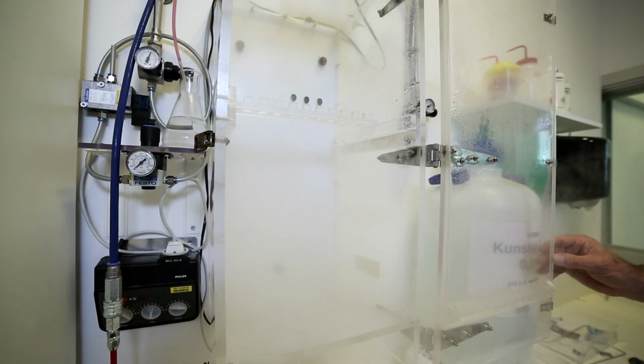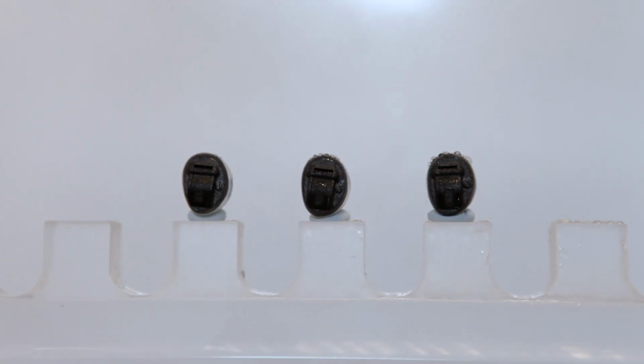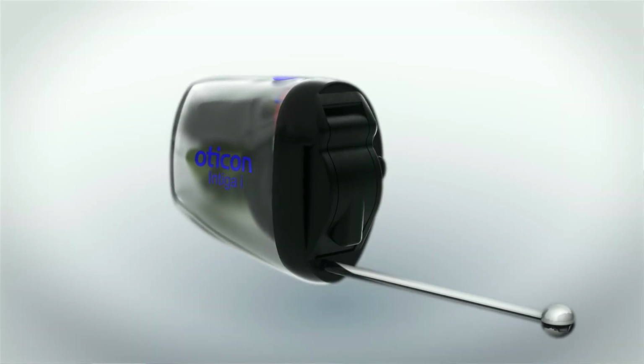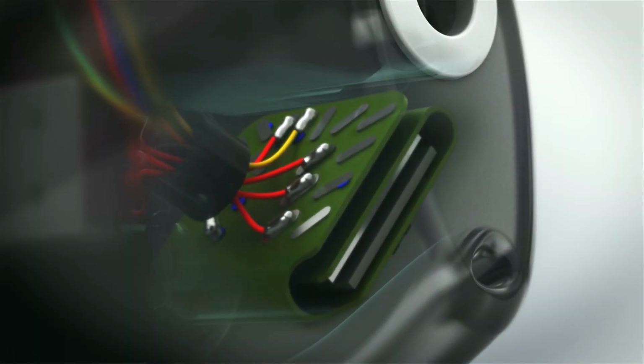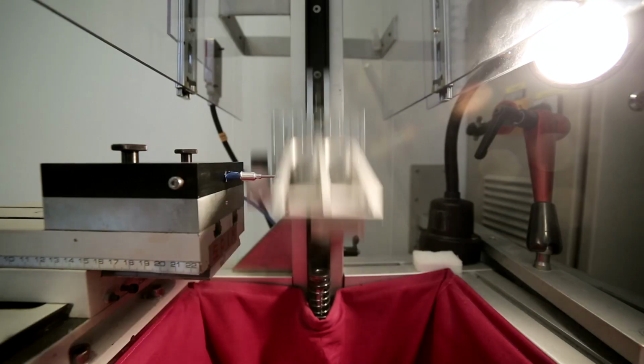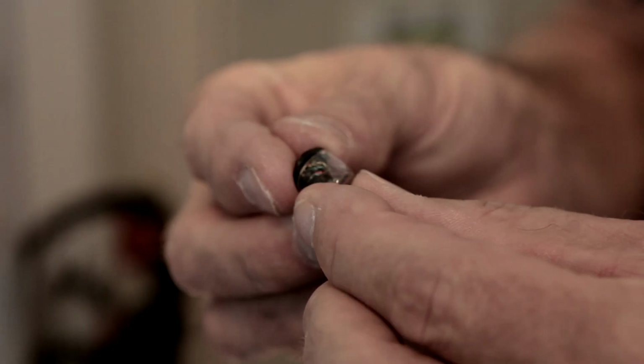Another point we improved is the receiver suspension, where we made a new internal support plane in the ear shell that will support the receiver if the instrument is dropped on the floor. The customer will benefit from these improvements - they will see that their instruments are not failing. They will just keep on working, and the sound quality will be stable throughout the lifetime of the instrument.